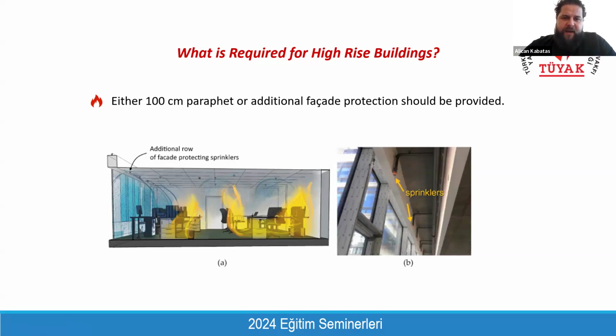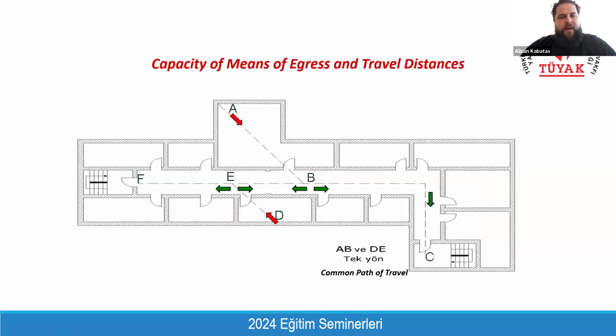And that's why if you don't want to have facade protection very closely located, 1.5 meter from the facade, and the spacing between the sprinklers should not exceed 2 meters, you need to design your facade to have solid 1 meter height parapets. And as you can remember, we have some common path of travel and travel distance limitations. And these limitations are changing with the existence of automatic fire suppression system, sprinkler system. That's why even if the sprinkler system is not mandatory within your building, the architects can prefer to have sprinkler system to use smoother common path of travel and travel distance limitations. It is up to architect's decision. As architects, you will define the existence, the provision of sprinkler system according to the travel distance measurements of your building.